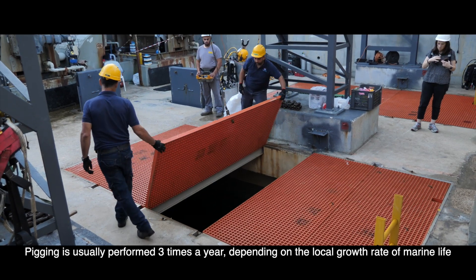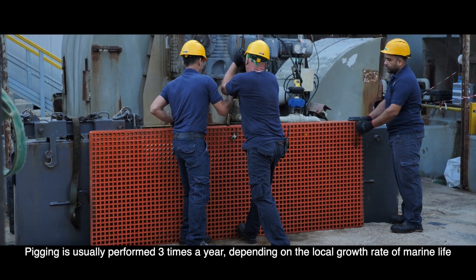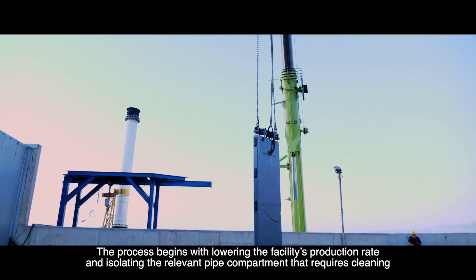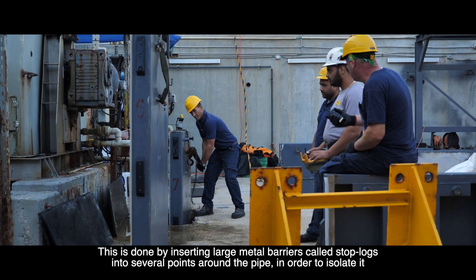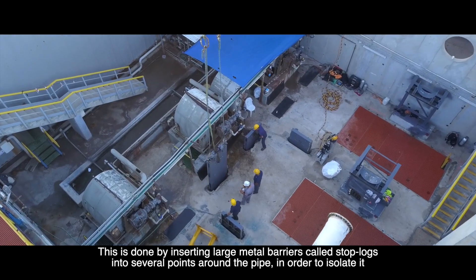Pigging is usually performed three times a year, depending on the local growth rate of marine life. The process begins with lowering the facility's production rate and isolating the relevant pipe compartment that requires cleaning, done by inserting large metal barriers called stop-logs into several points around the pipe.